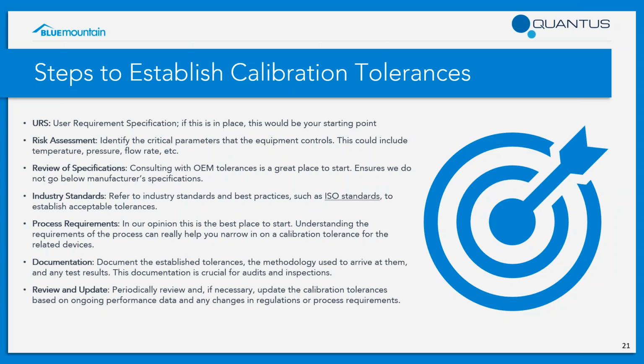So how do you establish these tolerances? Again, like I said, this is a big question that we get. The first one up there is a user requirement specification. This is not always in place for smaller instrumentation. Typically, we see URSs put in place for bigger systems like autoclaves or WFI systems or clean steam generators. So if you're really working on just a balance or a temperature transmitter in a system, you could start with a risk assessment.